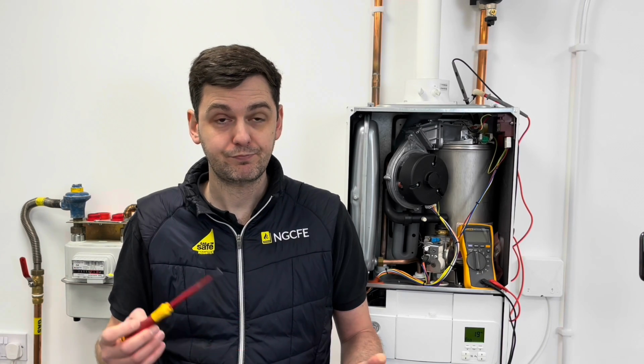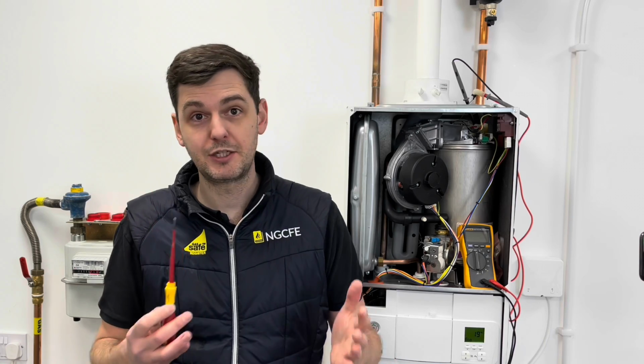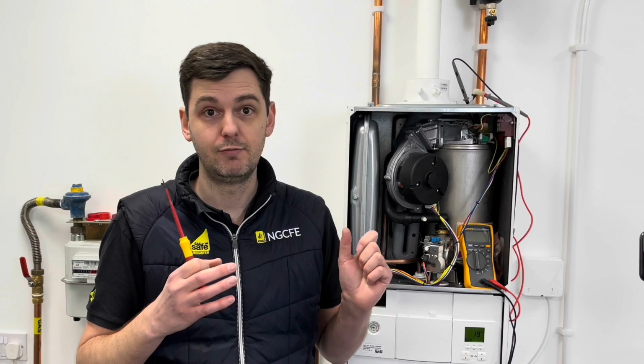So Mrs. Smith's called you, you've come out, you've gone through the process of establishing that the gas valve's okay, the spark generator's okay, you've checked the condensate trap, you've identified that that's clear, it's not causing the fault. So we suspect we've got a rectification issue. So what we're going to do is, exactly the same way we did with the Sabre rig, link out between the rectification probe and the lead with the multimeter and put it in series, and we're going to try and read what DC current we've got coming back.